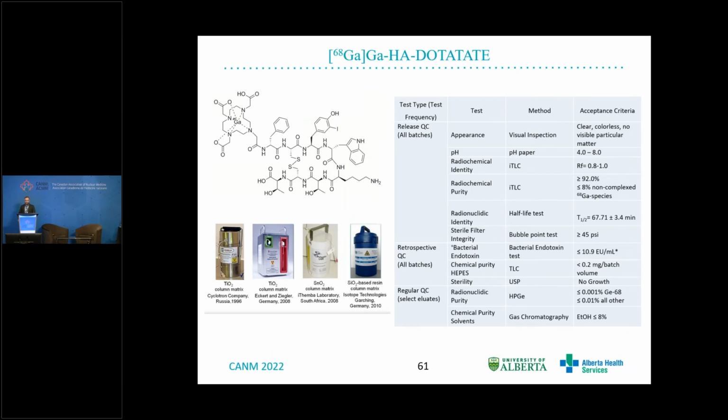And also we have the gallium DOTATATE here, where if you do it using a generator, you do need to test for the radionuclidic purity at least periodically, to check that you don't have germanium-68 breakthrough in your generator.